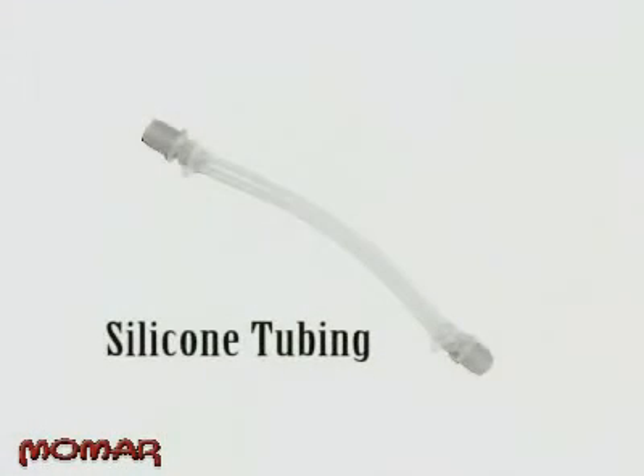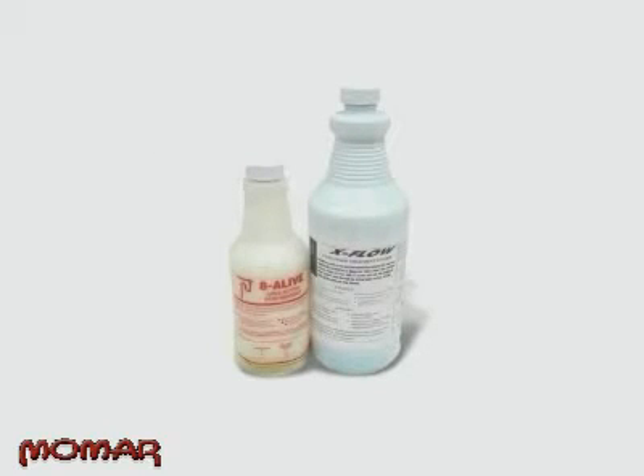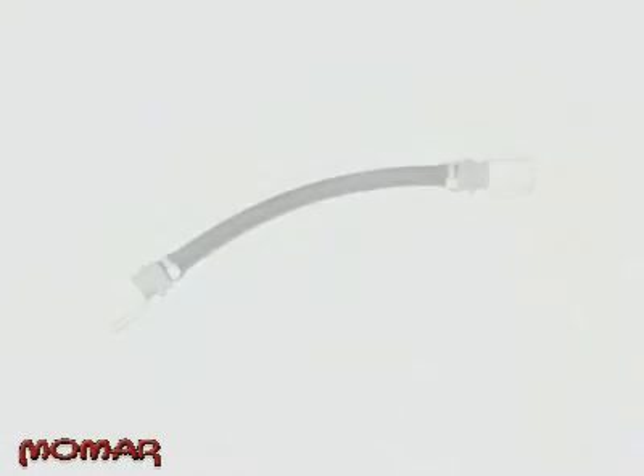Another innovation that maximizes the Maintain-It-All Pump's usefulness is its ability to be used with different types of tubing. The silicone tubing that comes standard works with all biological and enzymatic products, as well as products with a high pH such as drain cleaner, or low pH such as X-Flow. However, the silicone tubing is not compatible with solvent-based products like those used as lift station degreasers, so we offer Viton tubing for those applications.